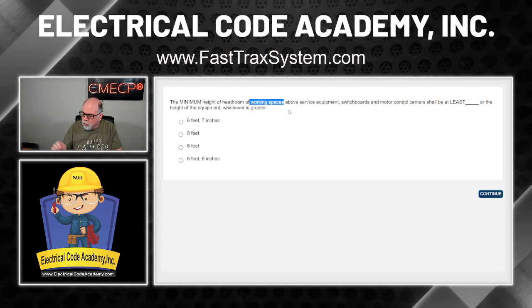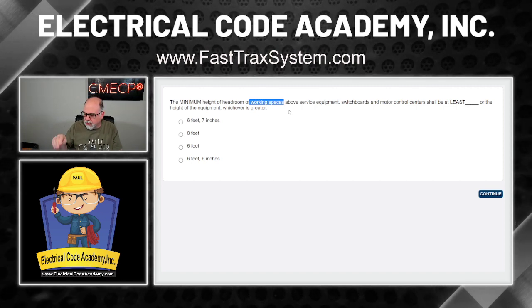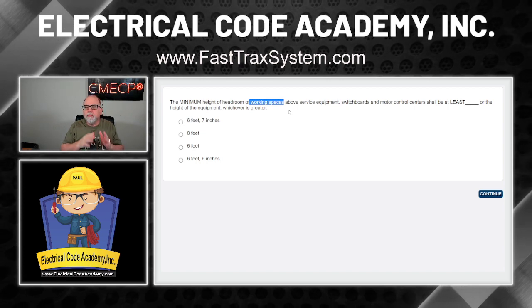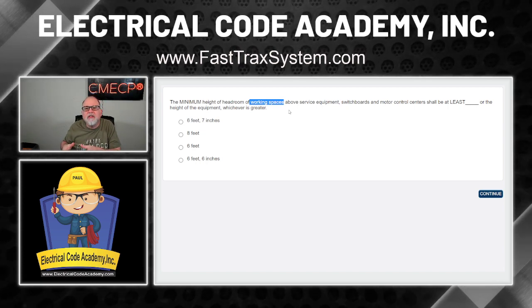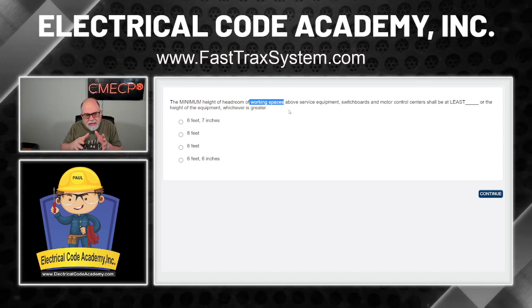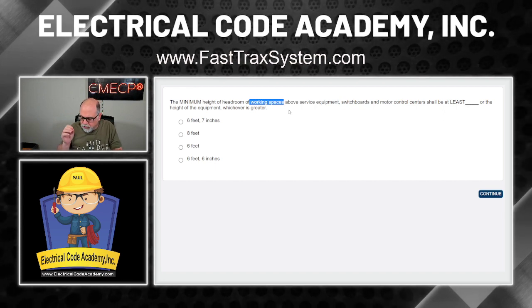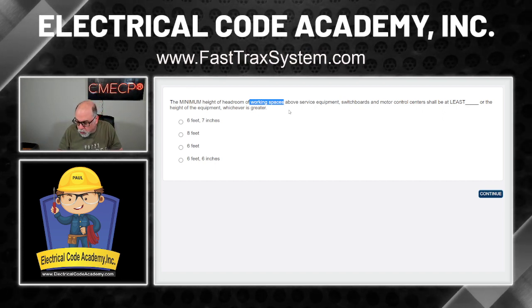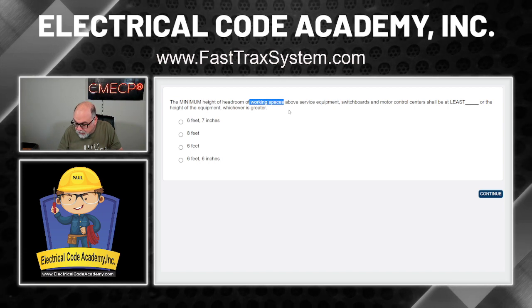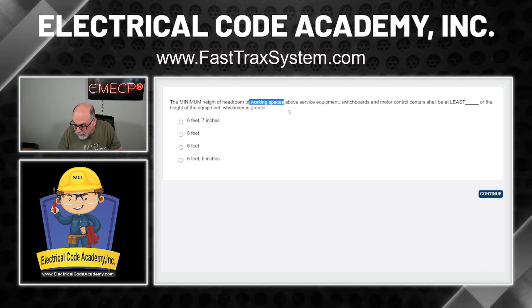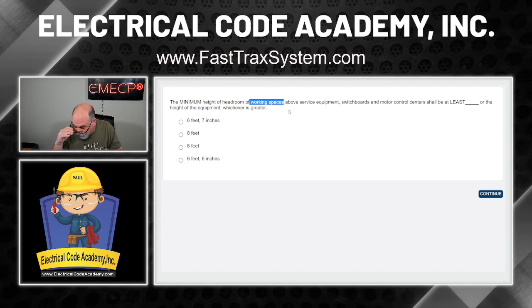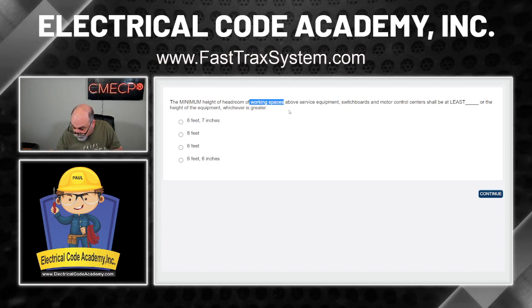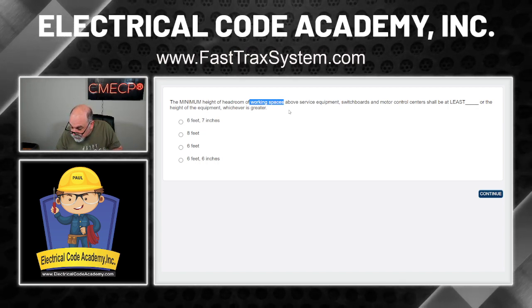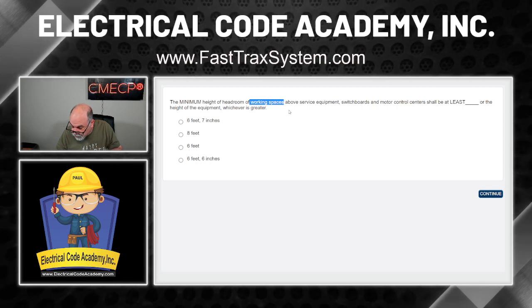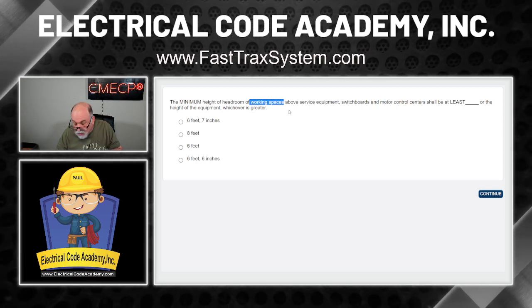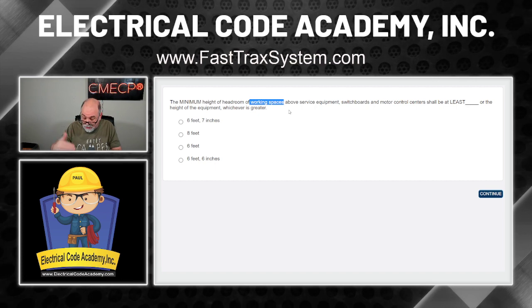Use it. Write down on that scratch paper all of the code sections that you want to go to based on your exploratory search into the actual index so that you don't have to keep going back and forth. For example, for me, I would be here under working space and I would write 110.26 down, right? And then looking down, I don't see anything else in here except for switchboards, and that also says 110.26. So that tells me I'm in the right place.